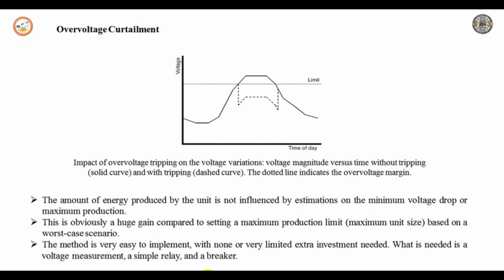The impact of over voltage tripping on the voltage and on the energy production is illustrated in this figure. You can see here that the difference between the solid curve and the dashed curve is proportional to the amount of power that is tripped. This implies that the area between the two curves is proportional to the energy not produced. In the case of wind power, this would be spilled wind. The maximum possible amount of production at any moment would result in a voltage exactly equal to the over voltage limit. This is shown as a dotted line in the figure. The area between the dotted line and the solid curve is necessary energy lost, whereas the area between the dotted line and the dashed curve is the unnecessary energy lost.